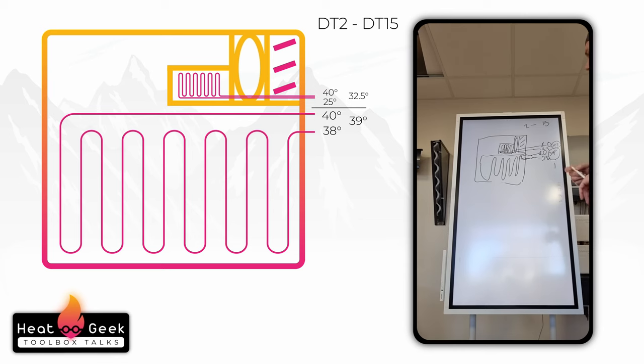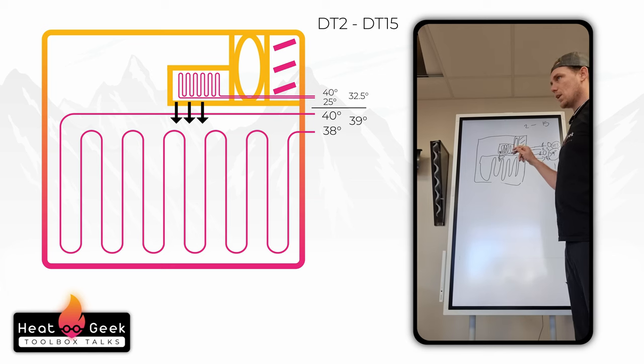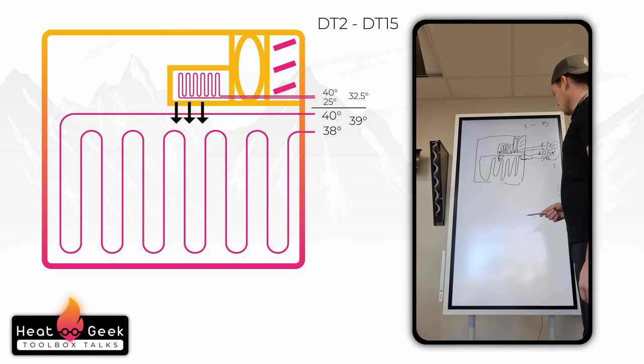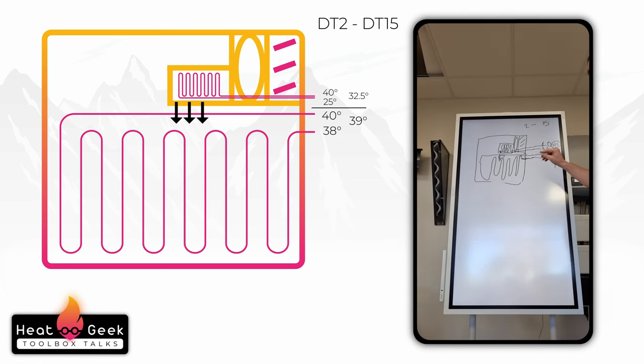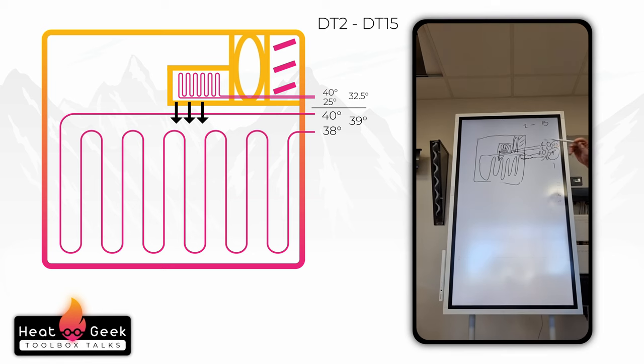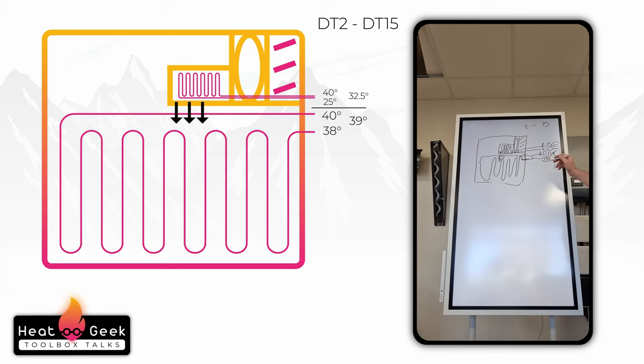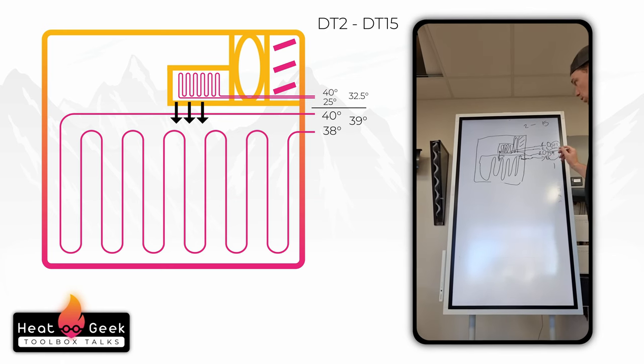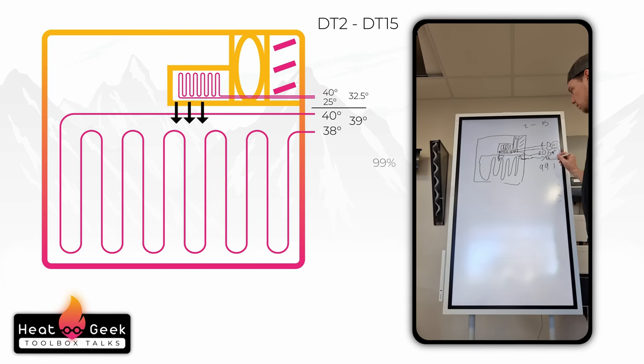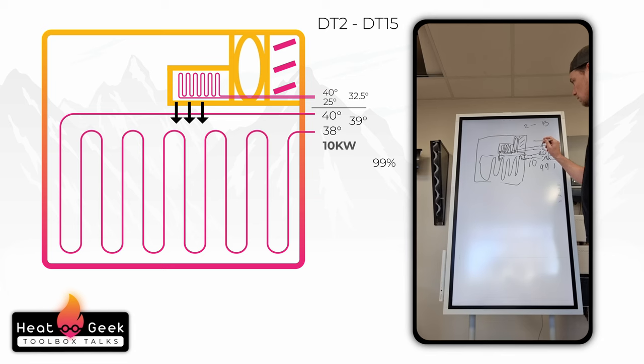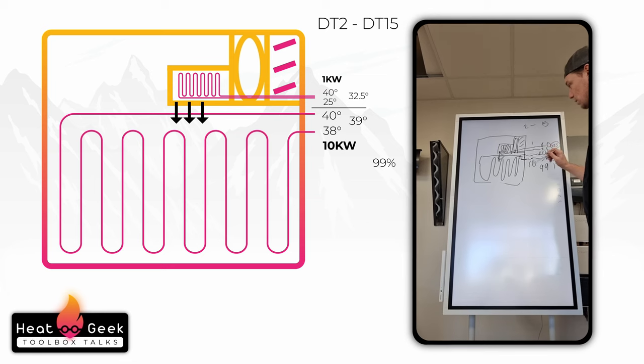Your heat loss does lose into these rooms as well. So as it tries to heat, you do lose it. But your largest heat loss is going to be the biggest room in kilowatts. Not the flow temperature - kilowatts are not the same. But your heat loss in the biggest room, so that would be your biggest one. So if you did that one at 100mm, this one's going to get like 99% of the flow because most of the kilowatts - let's say this is 10 kilowatts and this one's one kilowatt. So if this has 10 kilowatts and that has one and they have the same DT, this will have literally 10 times more flow.